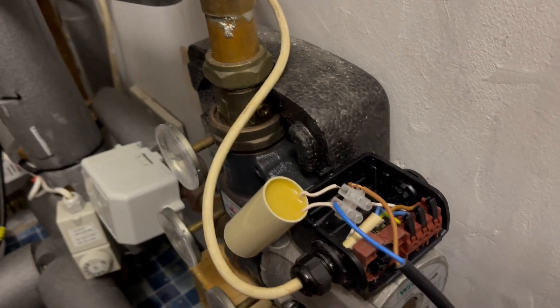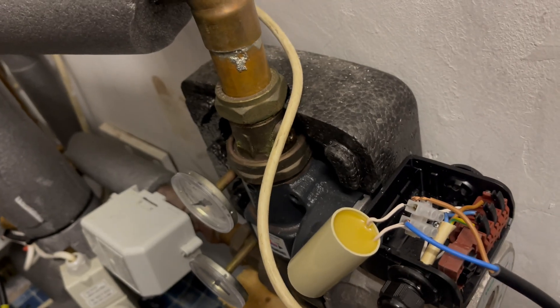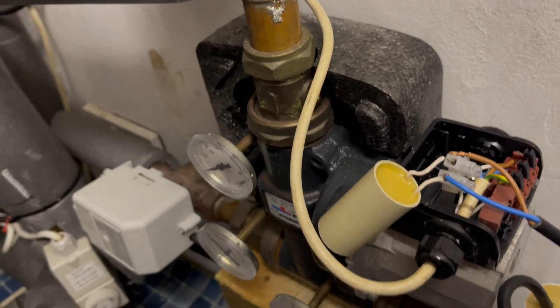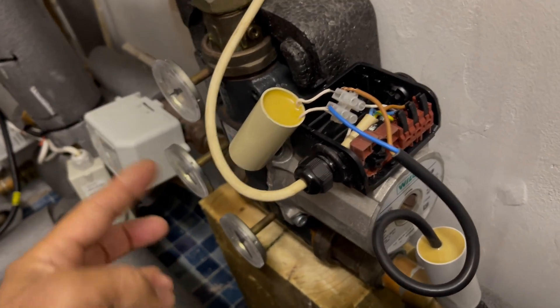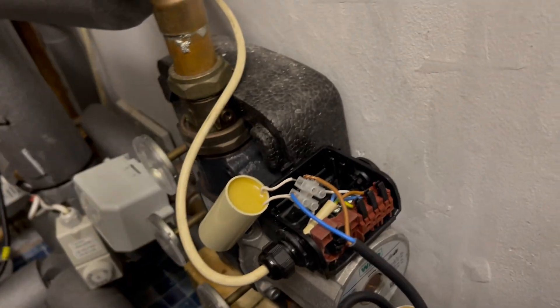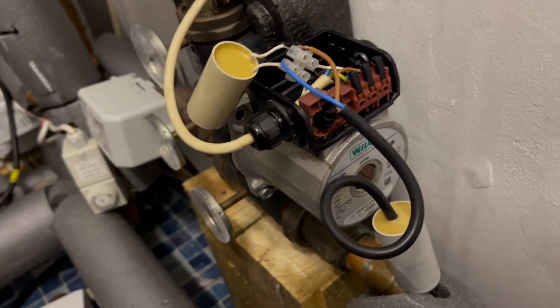This pump is part of what's called a Laddomat, which is a system used for wood-burning stoves where it basically circulates the water around the stove until it gets to about 50 degrees. Then the thermostat opens up and circulates it to the rest of the house. This pump is used to do the circulating, exactly the same as a central heating pump.